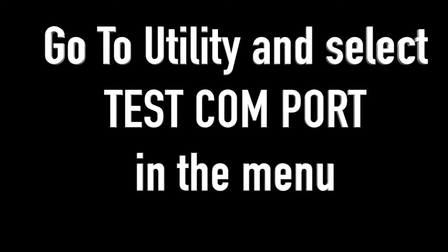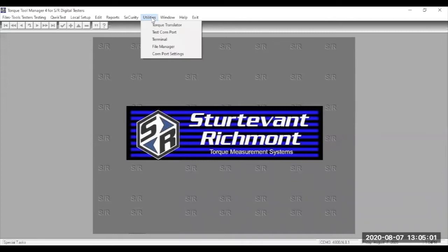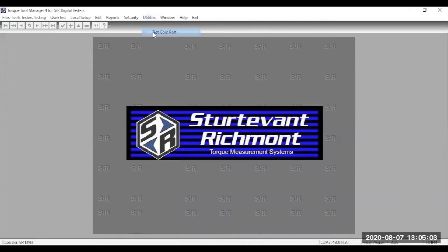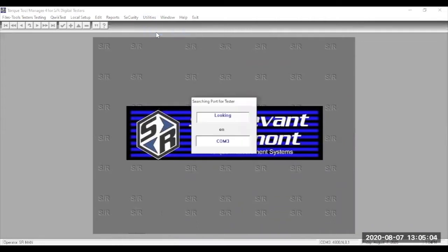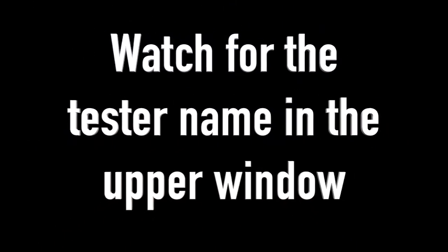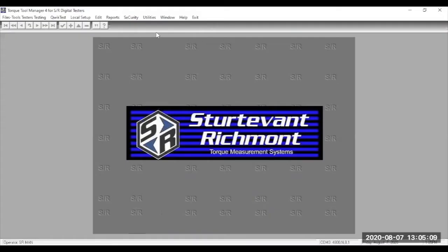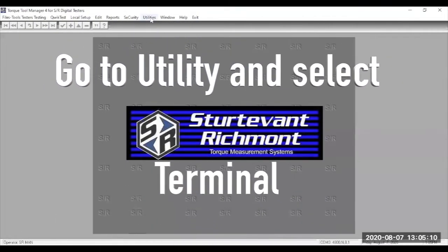the first step is to check to ensure that there's communication between the software and the tester. To do that, go to Utilities and then in the drop-down menu under Utilities, you'll see Test Comport. Click on Test Comport. You'll see two display areas appear in the window that pops up. In the upper window, you'll see the name of the tester appear. Now you know that the tester and the software are communicating.